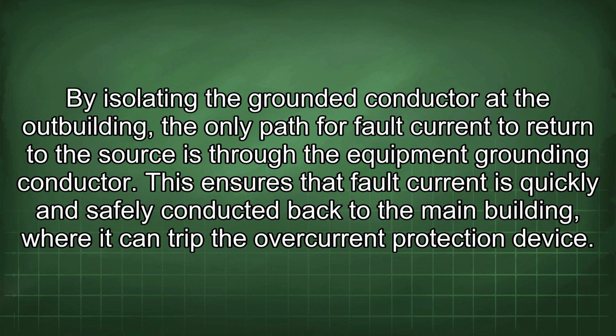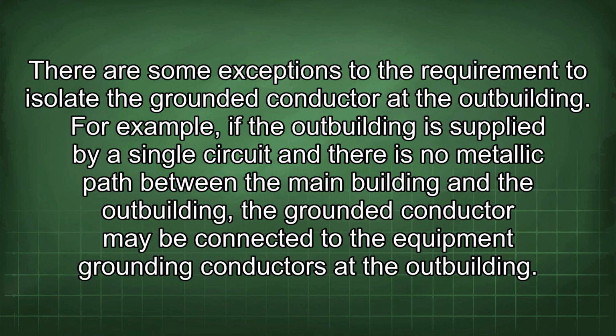By isolating the grounded conductor at the outbuilding, the only path for fault current to return to the source is through the equipment grounding conductor. This ensures that fault current is quickly and safely conducted back to the main building, where it can trip the overcurrent protection device. There are some exceptions to the requirement to isolate the grounded conductor at the outbuilding.